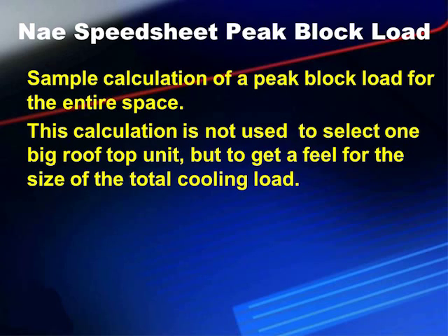Manual N Speedsheet, peak block load. Sample calculations of a peak block load for the entire space. The calculation is not used to select one big rooftop unit, but to get a feel for the size of the total cooling load. In other words, when you're done, you're going to want to do individual rooms and figure out how much air needs to go to individual rooms.